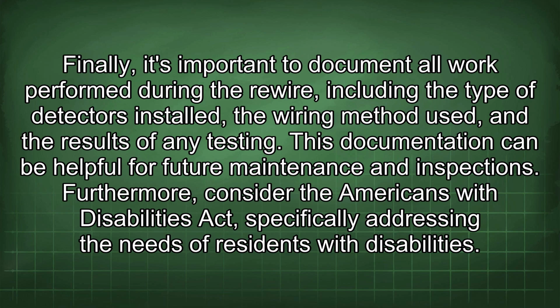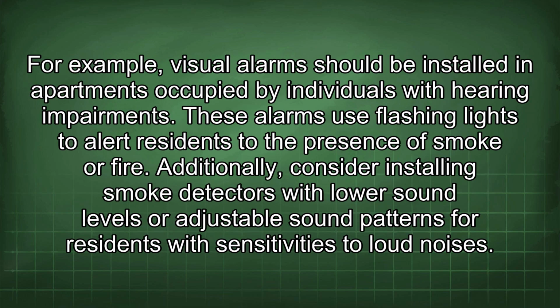Finally, it's important to document all work performed during the rewire, including the type of detectors installed, the wiring method used, and the results of any testing. This documentation can be helpful for future maintenance and inspections. Furthermore, consider the Americans with Disabilities Act, specifically addressing the needs of residents with disabilities. For example, visual alarms should be installed in apartments occupied by individuals with hearing impairments. These alarms use flashing lights to alert residents to the presence of smoke or fire. Additionally, consider installing smoke detectors with lower sound levels or adjustable sound patterns for residents with sensitivities to loud noises.